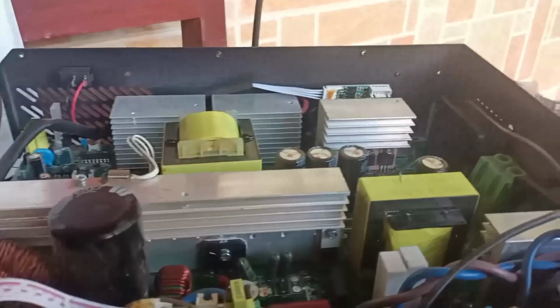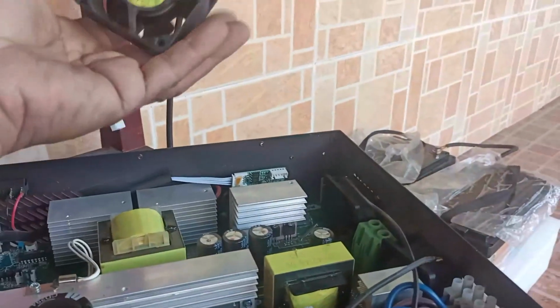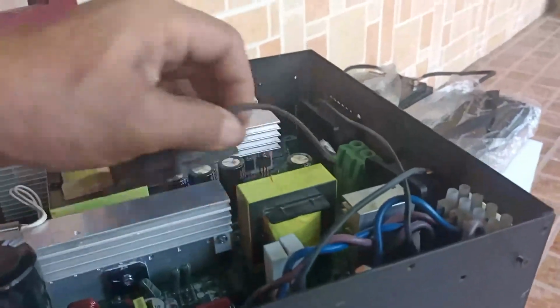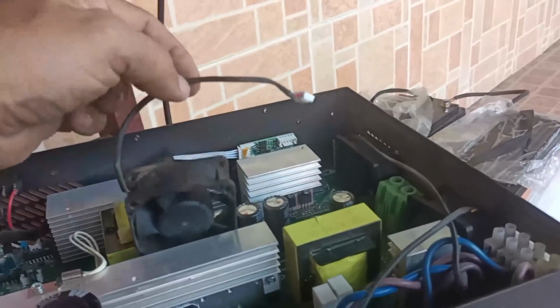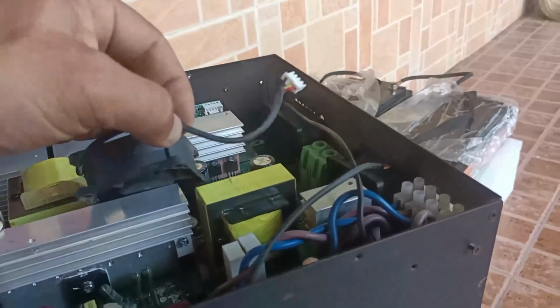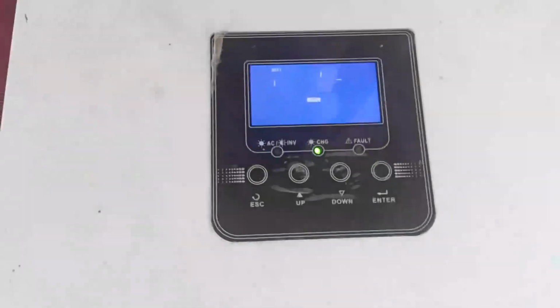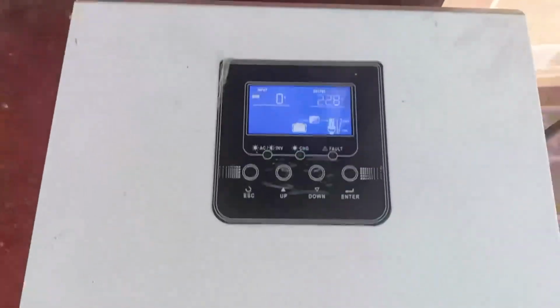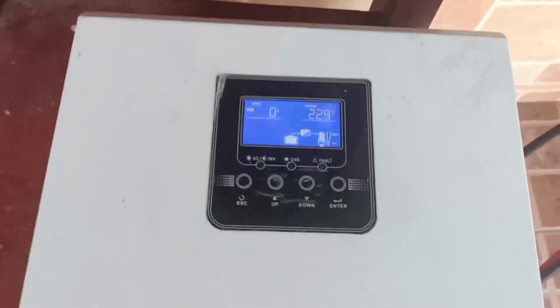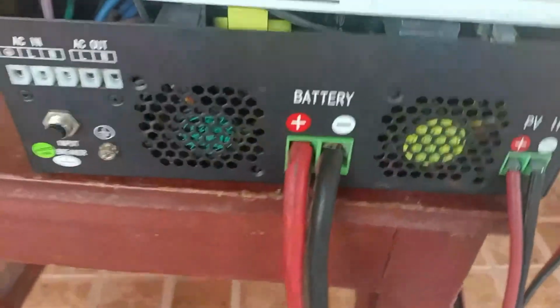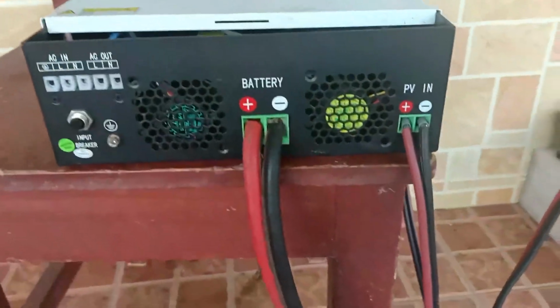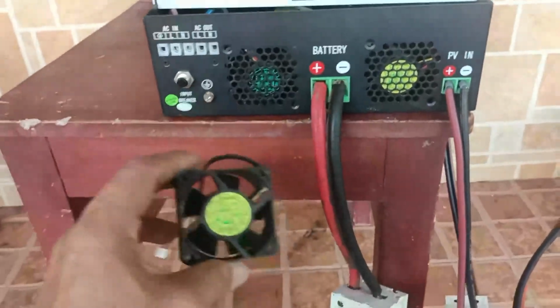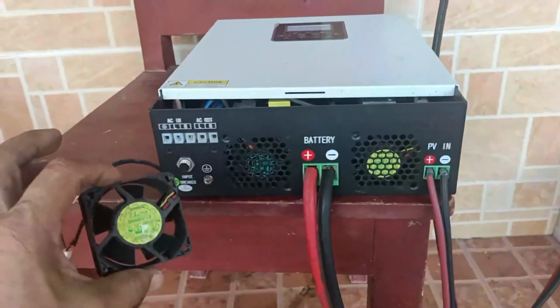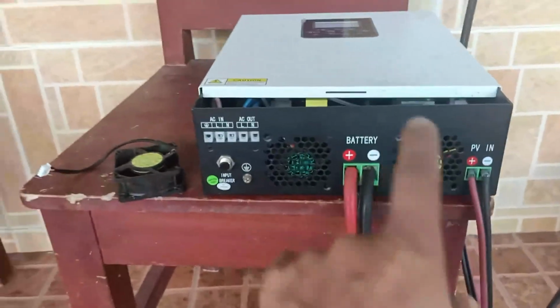A year, I think. So I would suggest that if this thing fails, then add a quick disconnect here so that they can be easily replaced without having to finagle the connector out of there. It's kind of difficult. So we'll test it now. I'll turn it on. So no error code. We fixed the inverter by replacing this fan with a different fan. I'm going to check what this is from Lazada and have spares just in case, for the future, because it will fail again.